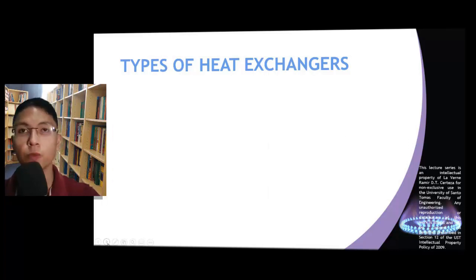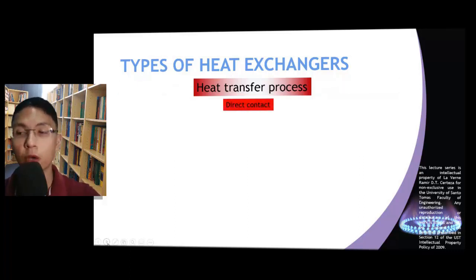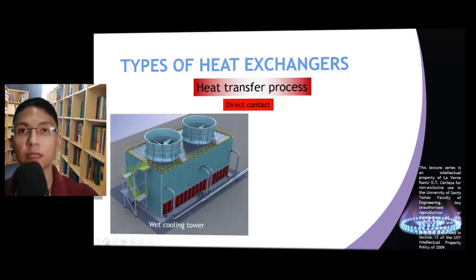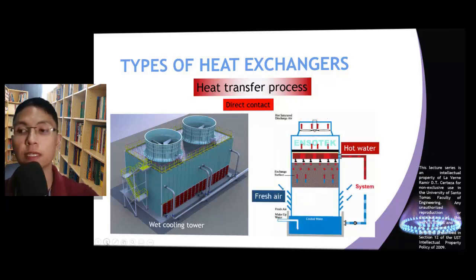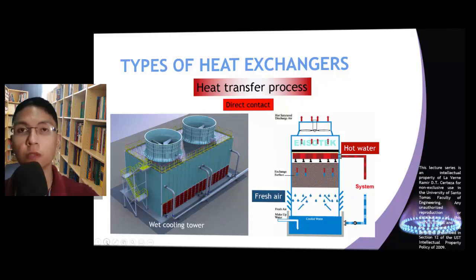Let us start by characterizing heat exchangers by their main heat transfer process. Under this criterion, we can categorize heat exchangers as either direct contact or indirect contact. In direct contact heat exchangers, there is no solid surface separating the hot and cold fluids. An example is the wet cooling tower, commonly found in thermal power plants and large commercial and industrial facilities. This heat exchanger works by forcing outside air into the cooling tower column, within which hot fluid is fed through spray nozzles at the upper portion, allowing convection heat transfer to occur.